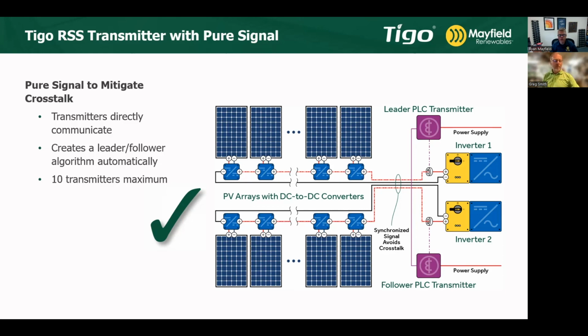Right now we're showing the leader PLC transmitter connected, with a purple line showing hardwired data communication between those two. If the leader PLC is on a different circuit breaker than the follower, and somebody throws the power supply on the leader but not the follower, you'd lose that signal on inverter number one, but inverter number two, the follower, becomes the leader. Yep, correct. That's the other big key—you actually physically connect those guys together.